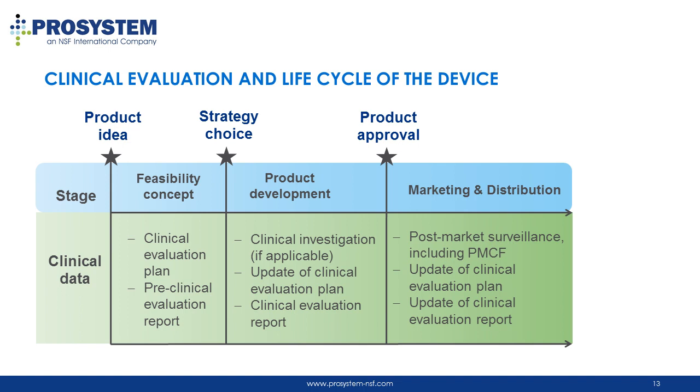Before the registration of the device, the clinical evaluation plan should be updated, if necessary, and a clinical evaluation report should be released. Finally, after the product approval, the manufacturer should have a post-market surveillance system in place, including post-market clinical follow-up activities. This data should then be used to prepare and update the post-market clinical evaluation plan and reports.